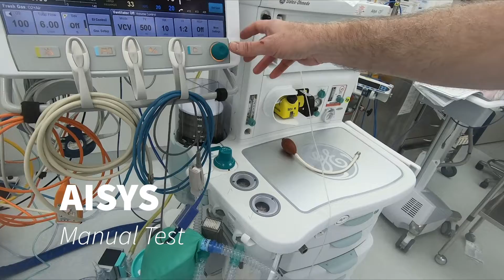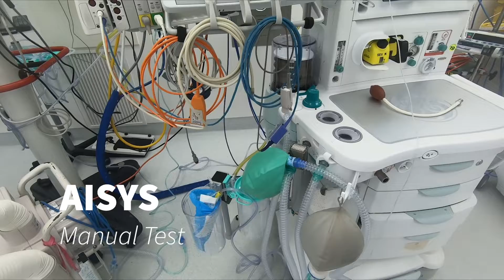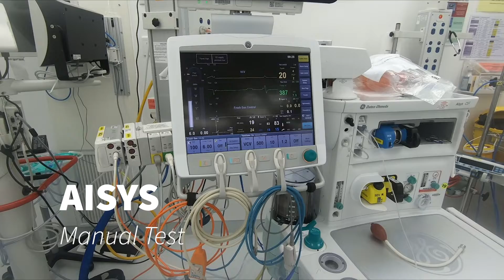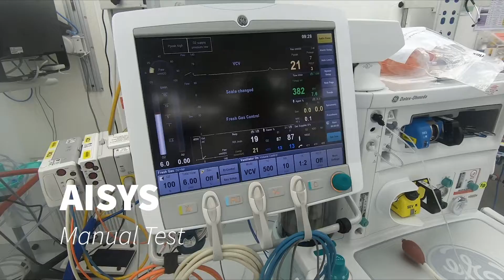So basically what we do when we do the ventilator test, after it's happy, we just give a good squeeze when it's delivering, and then we get the high pressure. So that's pretty much the same, and they will know how to do the low pressure one. And you could do that after you've been winding as well. Yeah. So will the ventilator come up now? Yep. Do it how you do it. It's fine.